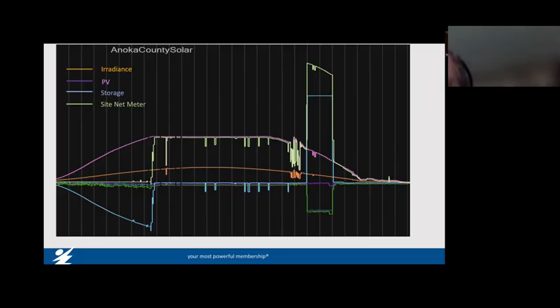So they start discharging, and you can see right here they discharged at full throttle, full output, 6 megawatts, for 2 hours. Then we get to the end of our control period, and they ramp back down—they're just about out of gas at that time anyway—and go into a resting state.